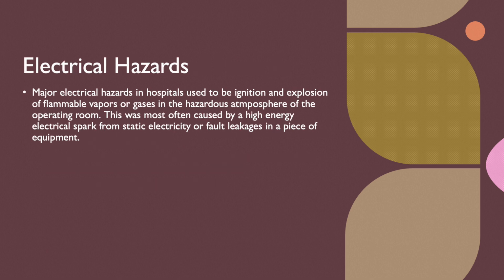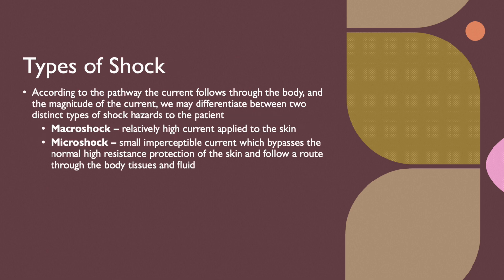When working in hospitals, the biggest electrical hazard is the ignition of gases or vapors from chemicals that can cause fire, often due to fault leakage, also known as leakage current. This means electricity flows into the insulation surrounding the wire, which normally keeps the current inside. When this leakage occurs, it can produce an arc, and if that arc hits something flammable, it can explode.